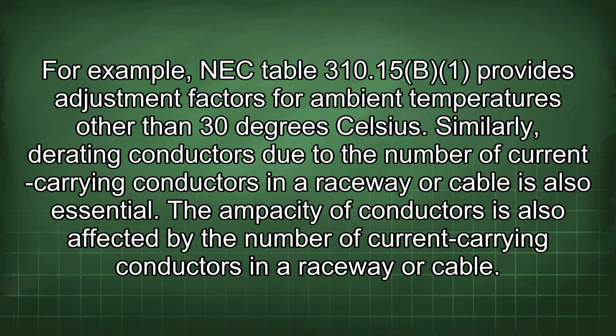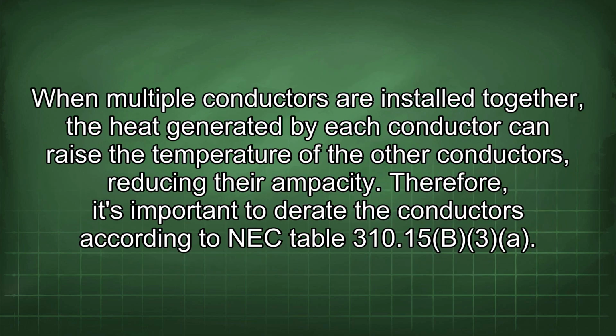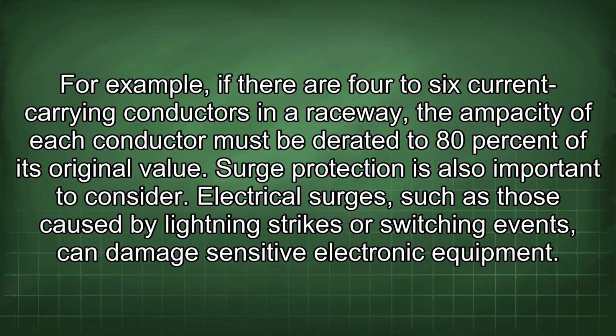Similarly, derating conductors due to the number of current carrying conductors in a raceway or cable is also essential. The ampacity of conductors is also affected by the number of current carrying conductors in a raceway or cable. When multiple conductors are installed together, the heat generated by each conductor can raise the temperature of the other conductors, reducing their ampacity. Therefore, it's important to derate the conductors according to NEC Table 310.15(B)(3). For example, if there are 4 to 6 current carrying conductors in a raceway, the ampacity of each conductor must be derated to 80% of its original value.